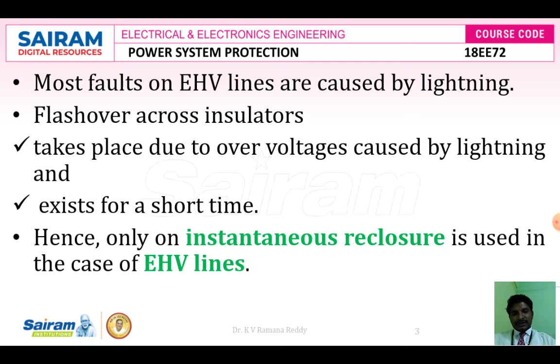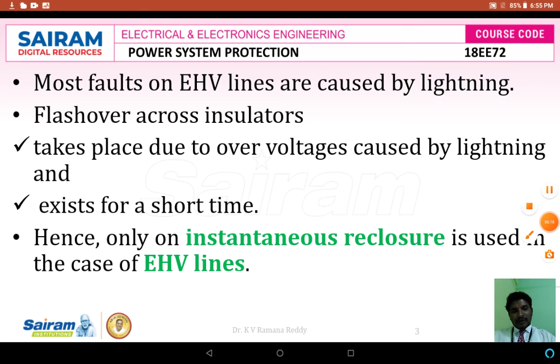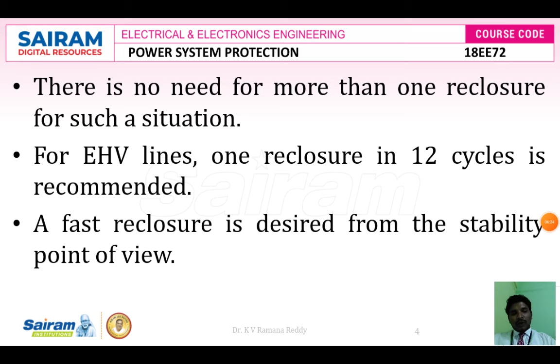because suppose it is the case where there exist lightning strokes or tree branches falling on the transmission line. Due to these two reasons, definitely it requires only one circuit breaker, not more than one circuit breaker. That means it requires only one recloser, that is enough to deal with problems like over voltages or over current. It's because of lightning strokes, tree branches, or any other human intervention actions which take place to make a short circuit on one line, two lines, or three lines, with respect to the ground or without respect to the ground.